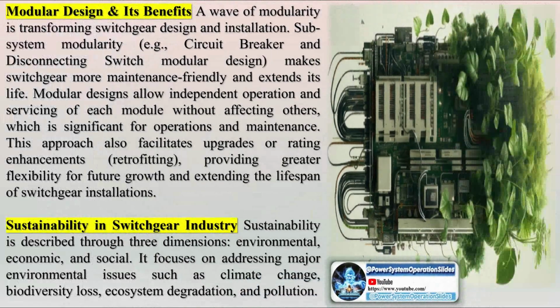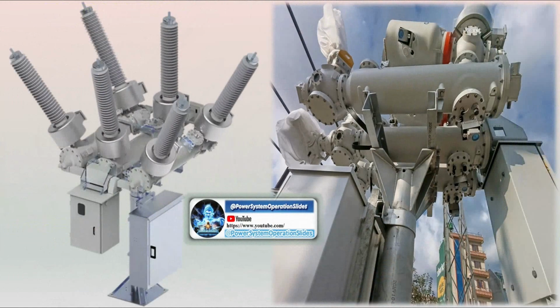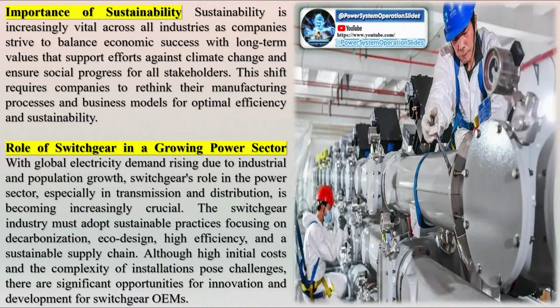Gas-insulated switchgear has been evolving since the late 1960s and has become increasingly popular due to several key advantages. GIS switchgear is highly resistant to environmental conditions like moisture, dust, and salt air, which enhances its reliability and uptime. This makes it suitable for harsh environments such as coastal or desert areas. The components of GIS are sealed in a gas-filled enclosure, preventing exposure to the surrounding environment. This significantly reduces maintenance requirements since regular testing and inspection are not needed.